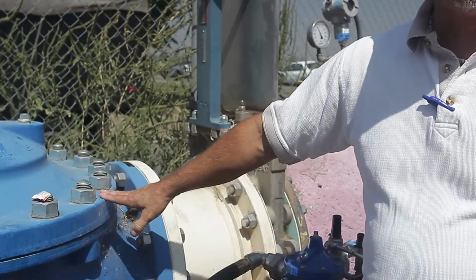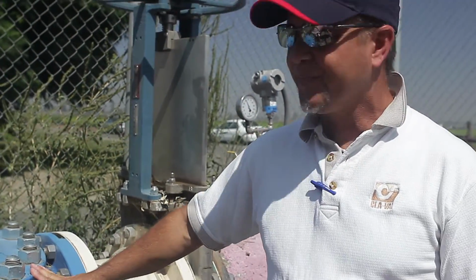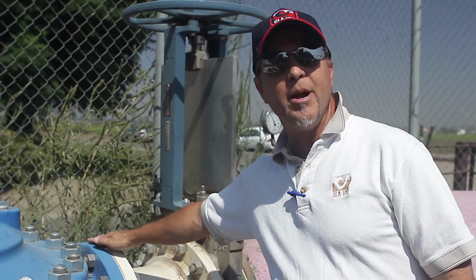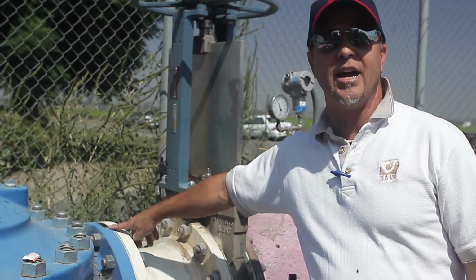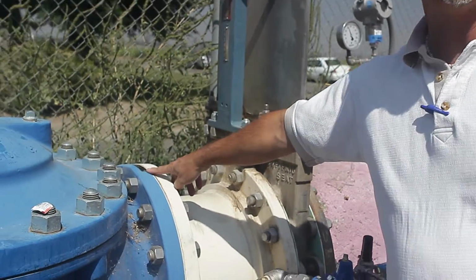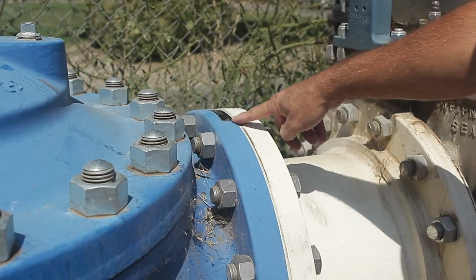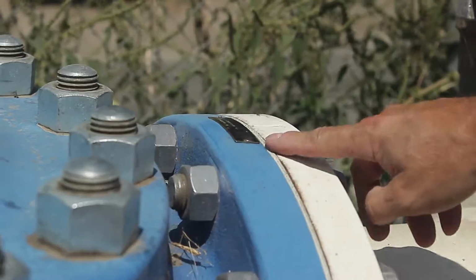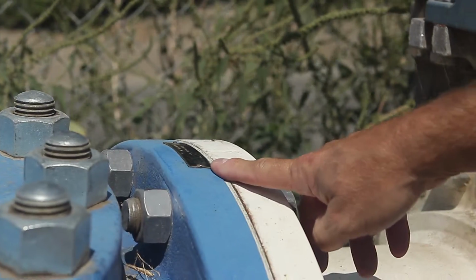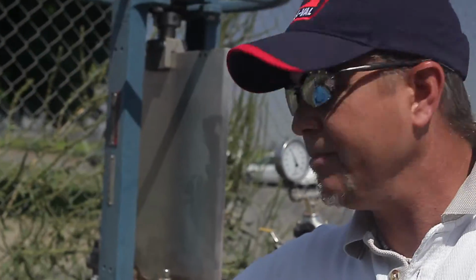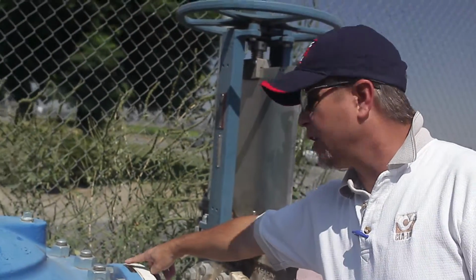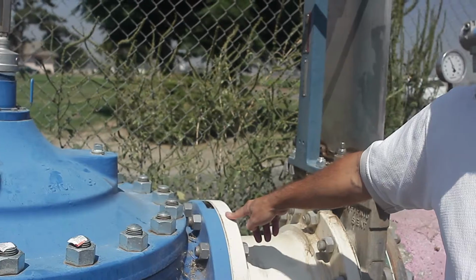Let's go over the 16-inch valve first. All of the information on this valve is on this brass tag right here. It says inlet in 4 different languages. The top number tells us the size, the catalog number, the stock number, and also a 2-letter date code. It tells us when the valve was manufactured.